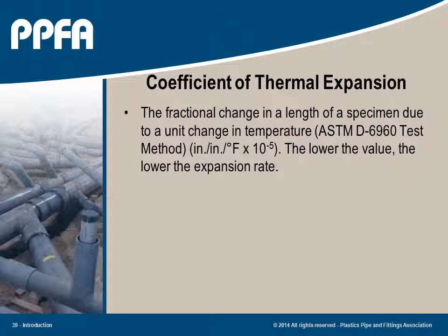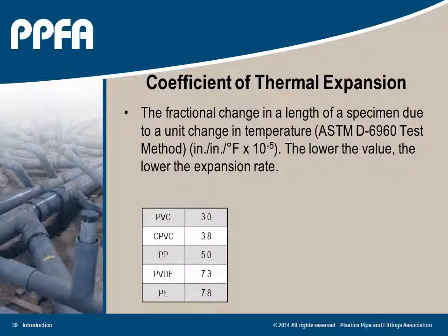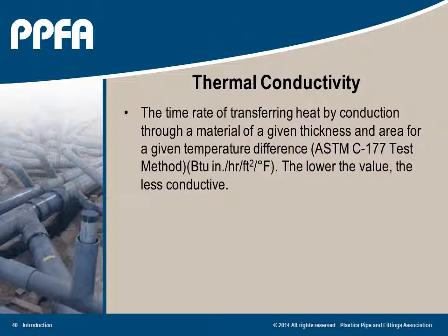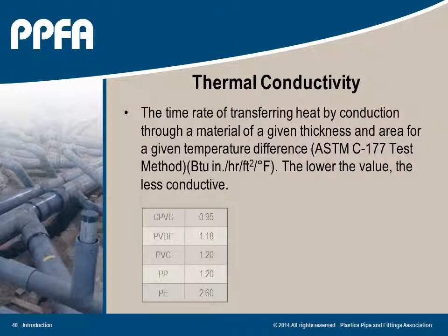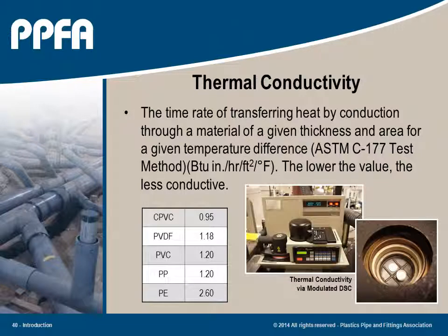Due to a larger coefficient of thermal expansion, thermoplastics expand and contract at a greater rate than other piping products. Almost all thermoplastics, when compared to other piping materials, have much lower thermal conductivity, resulting in reduced or no need for piping insulation and significantly reduce the possibility of developing condensate or sweating on the pipe exterior.